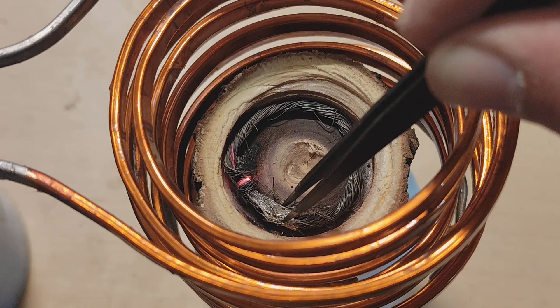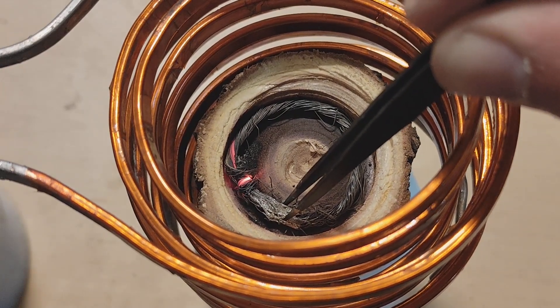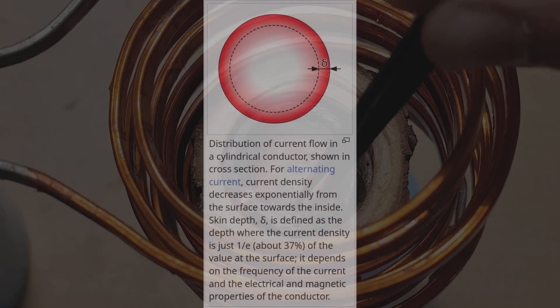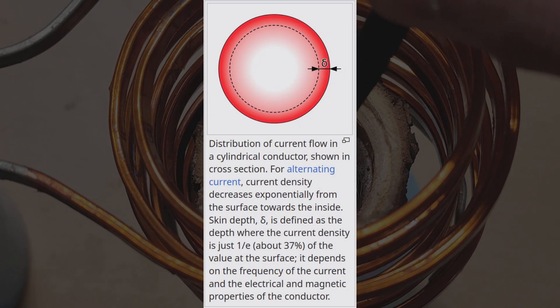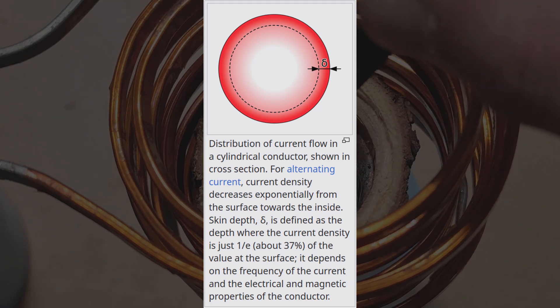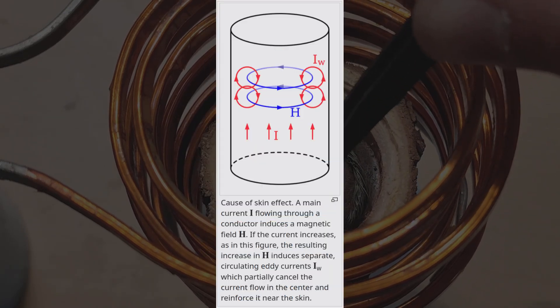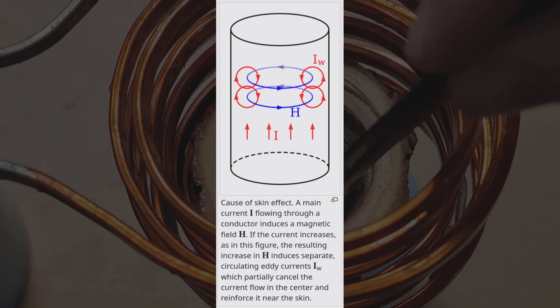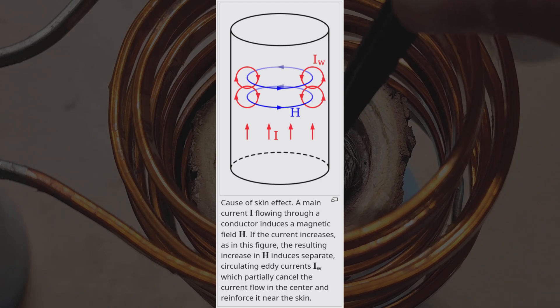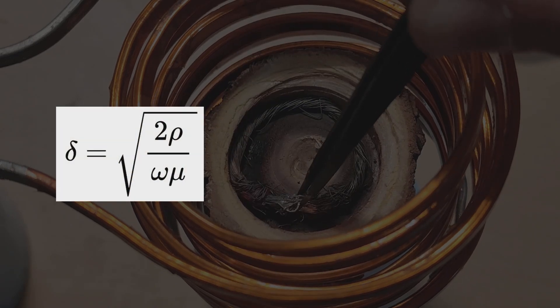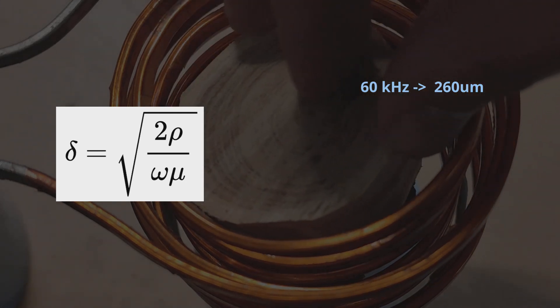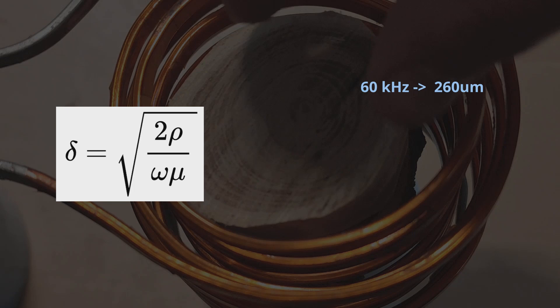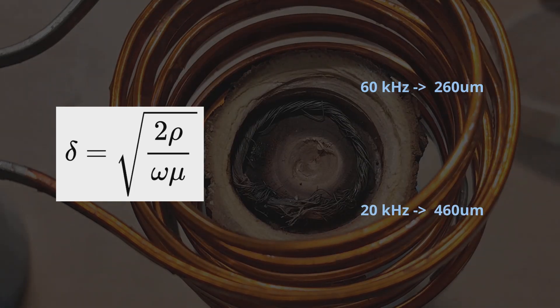There's multiple reasons for this. One is that in general, it's tied to the skin effect. In case you're not familiar with the skin effect, it's basically just a phenomenon that makes all the current flow, or almost all the current flow, on the outside layer of the conductor. And this basically just increases the resistance of our wire, just because there's less cross-section through which the current actually can flow. For example, at 60 kilohertz, the skin depth is about 260 microns, while at 20 kilohertz, the skin depth is almost half a millimeter.